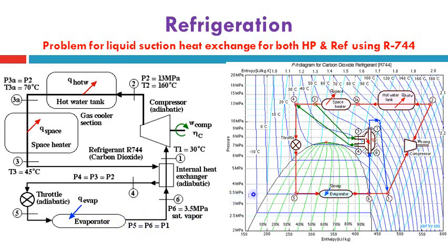We're using the line of 3.5 megapascal to get these points. Then we can estimate this temperature line, which is 0 degrees. So the superheating is equal to about 30 degrees Celsius, from 0 to 30, from point 6 to point 1. However, then we will go with adiabatic compression to point 2, which is indicated here by temperature and pressure.